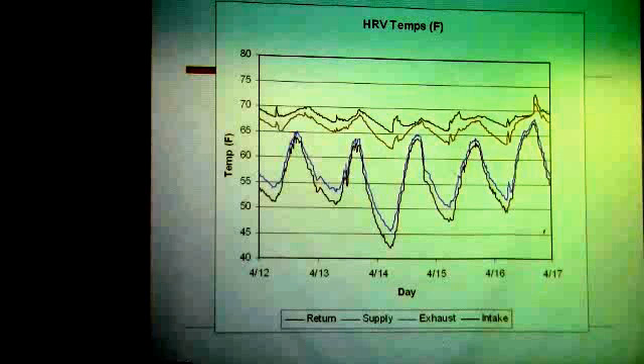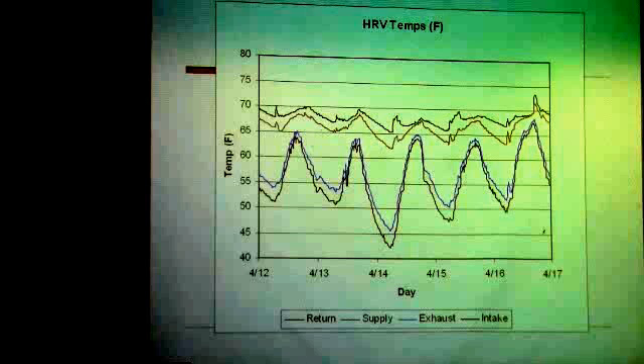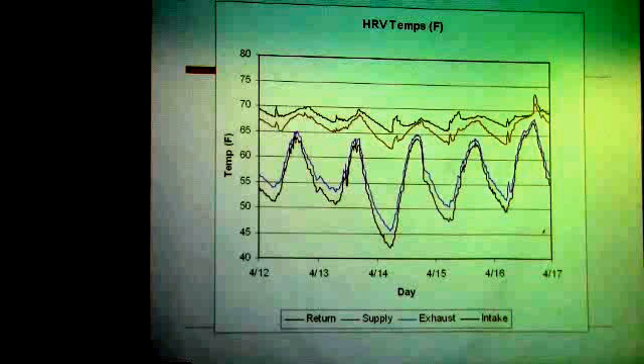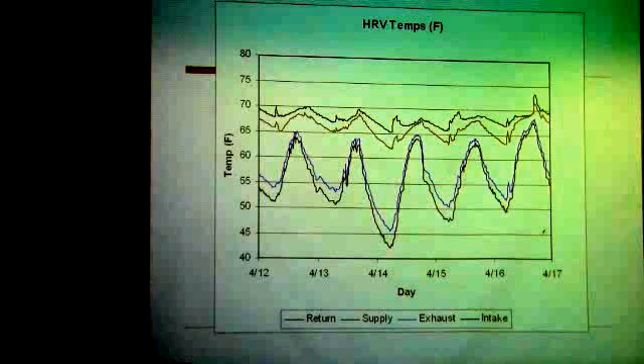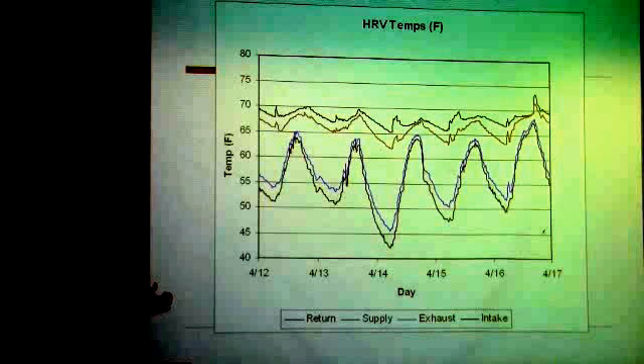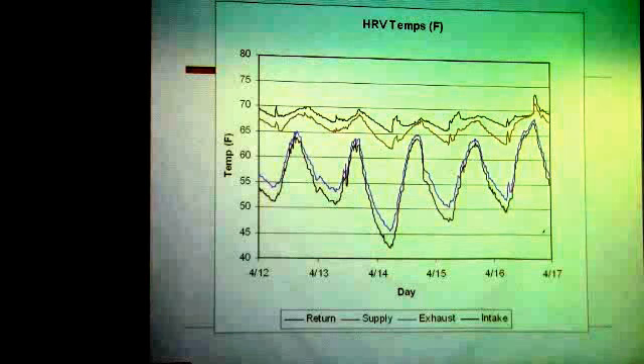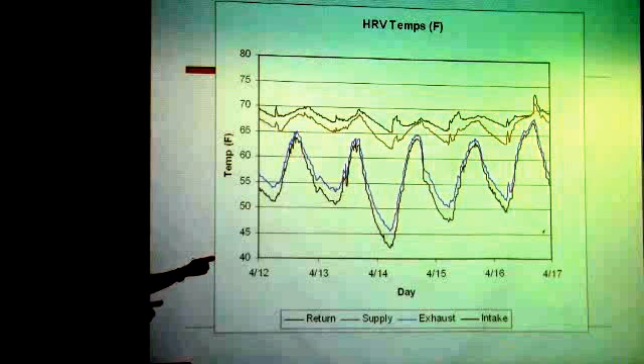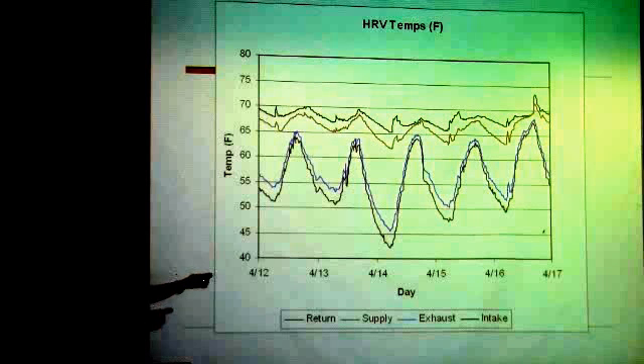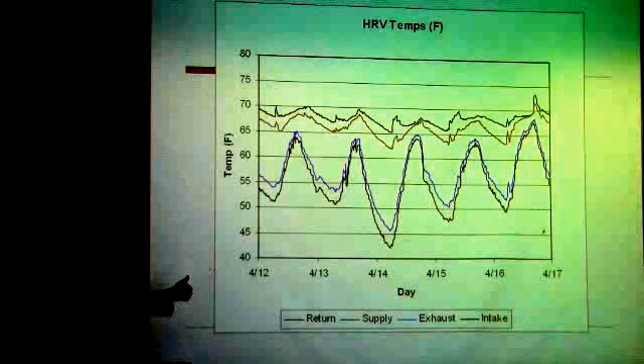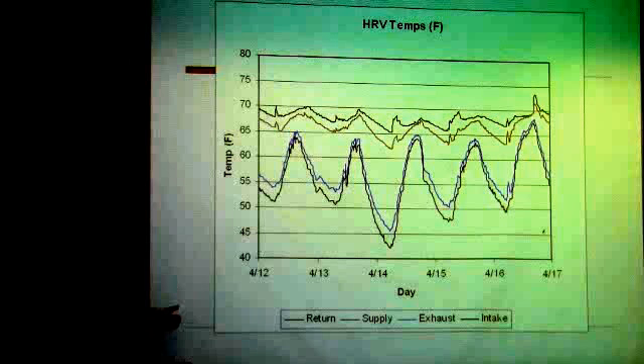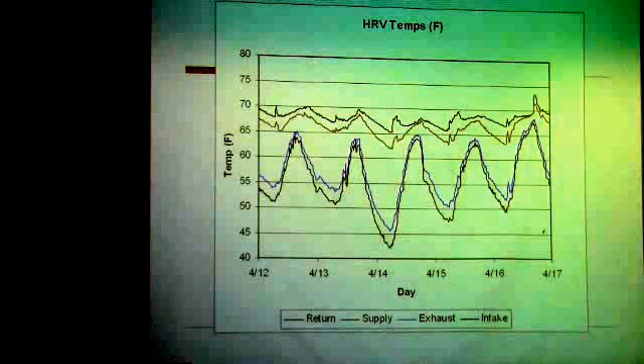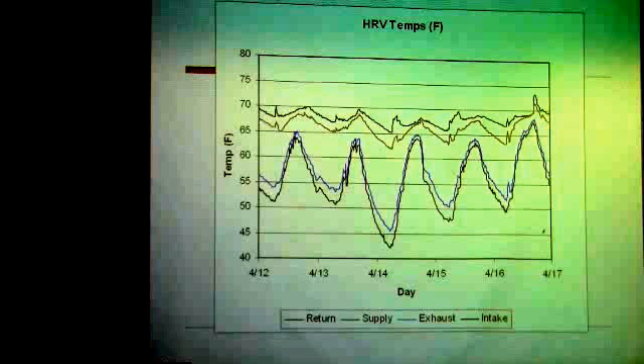Any questions on that, or did I breeze over that pretty fast? But anyway, like I said, that's taking the temperature of the 4 ports. So on the HRV, there are 4 ports. One's the fresh air supply, and then that supply goes through the heat exchanger and goes to the house, to the rooms, bedrooms, and say the living room. And then the other 2 ports, it's the return air coming from the bathrooms and kitchen, going into the port and going through the heat exchanger, and then to the exhaust.